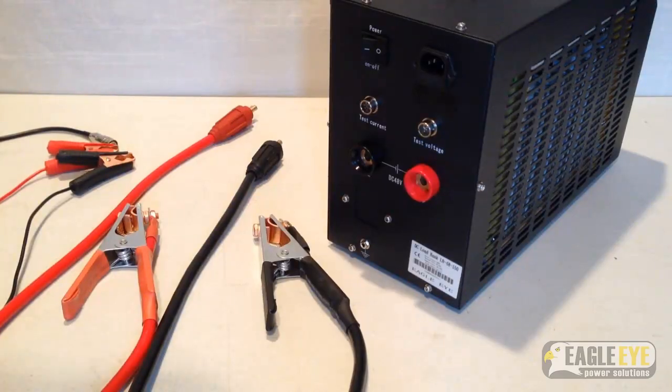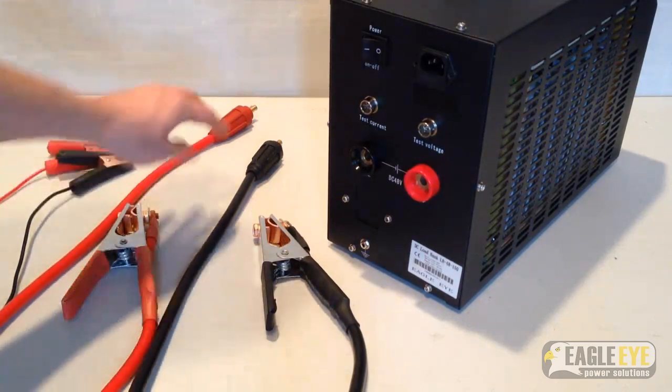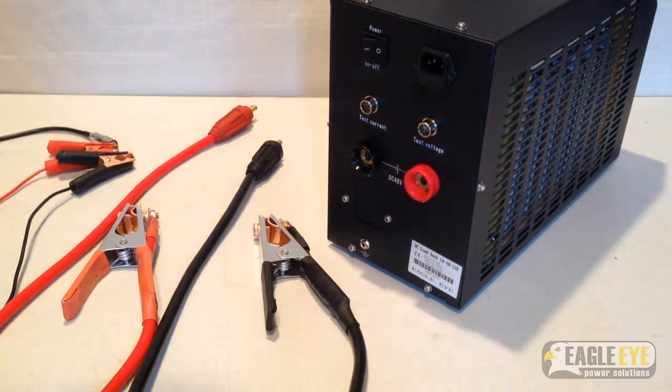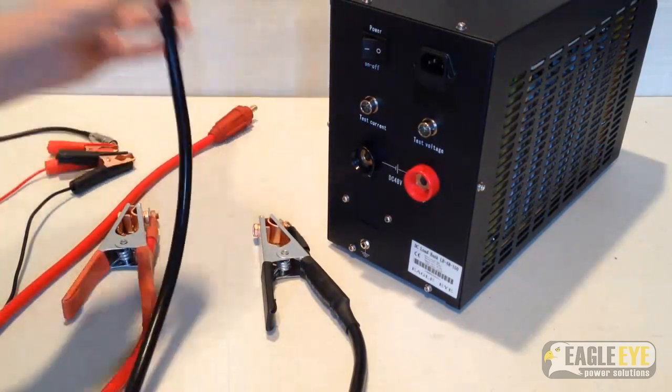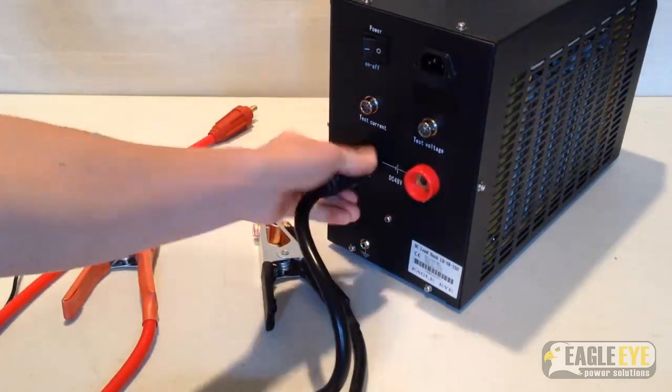The first step to setting up the load bank is connecting the discharge and voltage cables from the load bank to the battery string. Always be sure to connect the cables to the load bank before the batteries. If the discharge cables were connected to the batteries first, the ends of the cables could come in contact and create a short circuit.